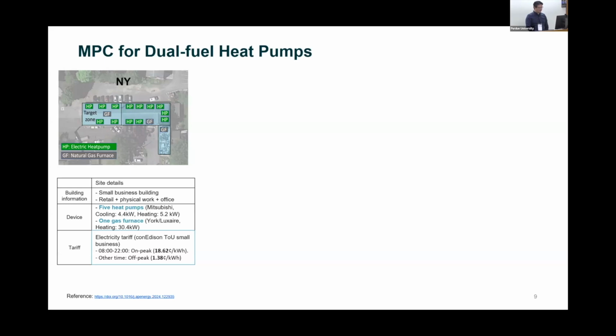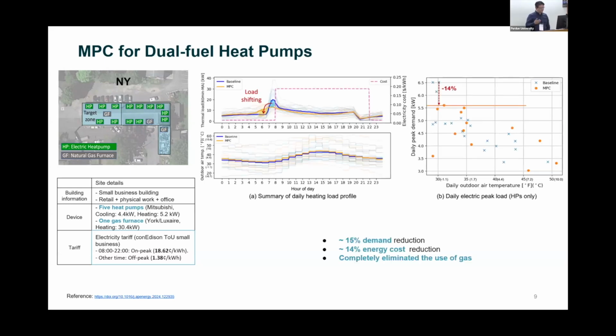So we repeated this kind of testing again and came up with around 14% energy cost reduction, while reducing the demand. And one thing that I'd like to emphasize is we completely eliminate the gas usage of the dual fuel system. What's happening for the dual fuel system in the existing setup? They are using so-called droop control.